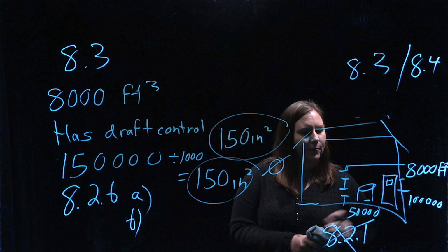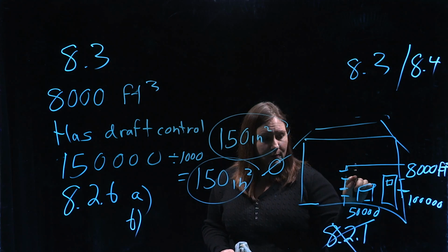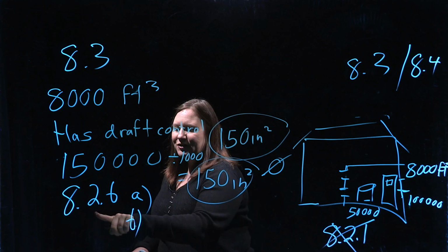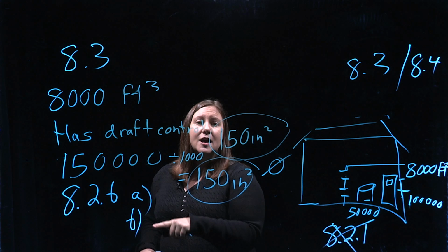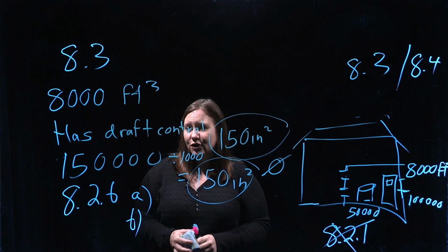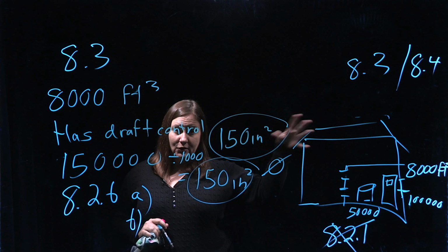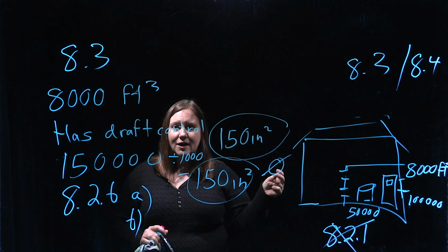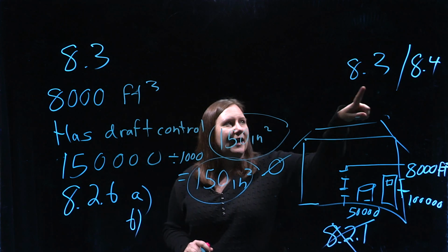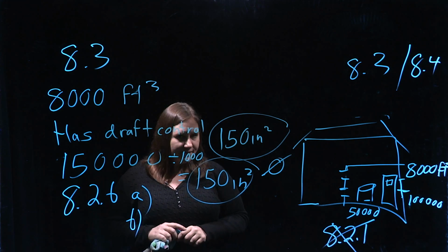But if we get a zero, then you have to consider, is that inside of a room or is it just an open building? And if it's inside of a room, then that means we have to allow communication in between the structure and the enclosure, and that's from 8.2.6, A for all appliances, B for having draft control devices. Okay, so that's super easy for when we're talking about a structure that does not comply with 8.2.1, when we're talking about appliances that do not have the combustion air brought in from outdoors by the system as a whole. So if it's a direct vent, a 2-pipe high efficiency furnace, any of that, we're not considering it, but anything else, we first refer to 8.3, 8.4, and then if it turns out we get a 0, then from there we can move on to 8.2.6 if it's inside of an enclosure.